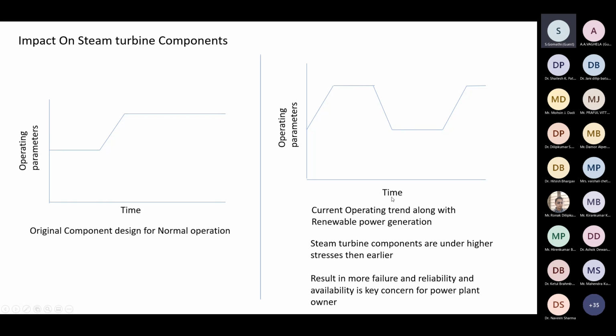The components which are already under high stresses will get cyclic load, because steam turbines are mainly made for base load power plant operation. This results in high stresses, and that causes low cycle fatigue, failure of high stress components like blades. It may not fail instantaneously, but if you do these things on an average daily basis, there will be a challenge to steam turbine components.